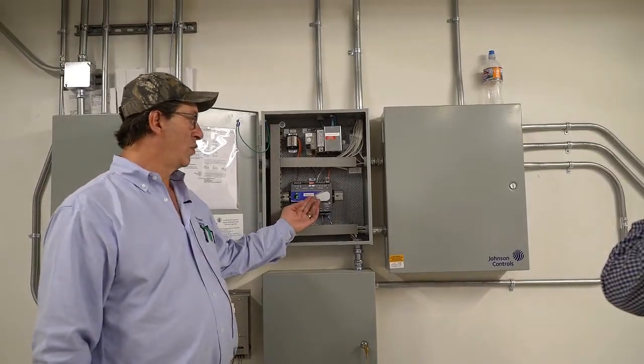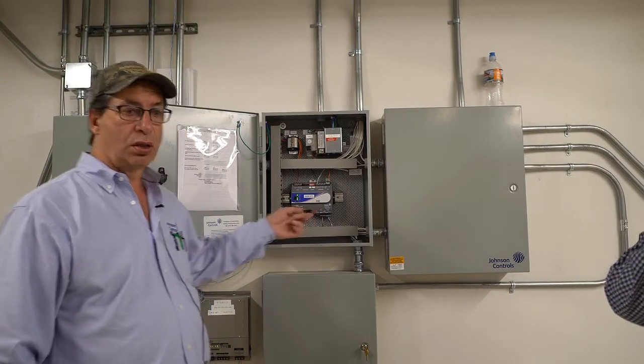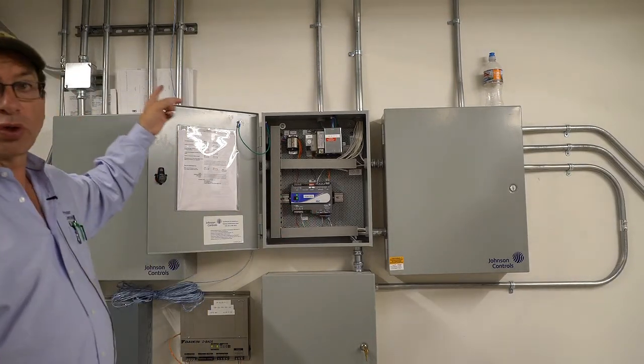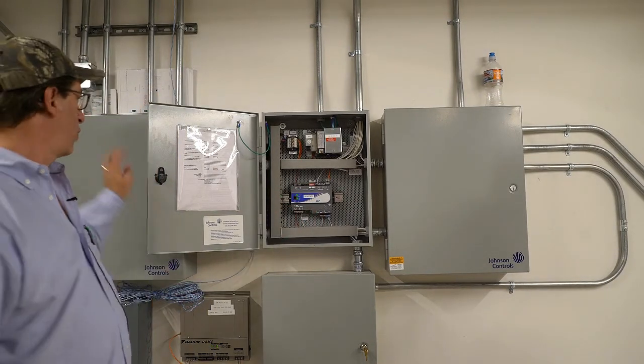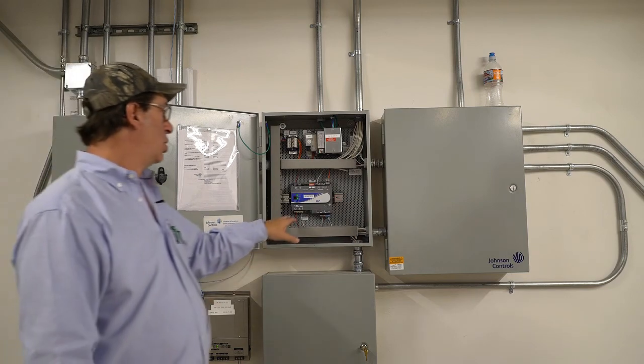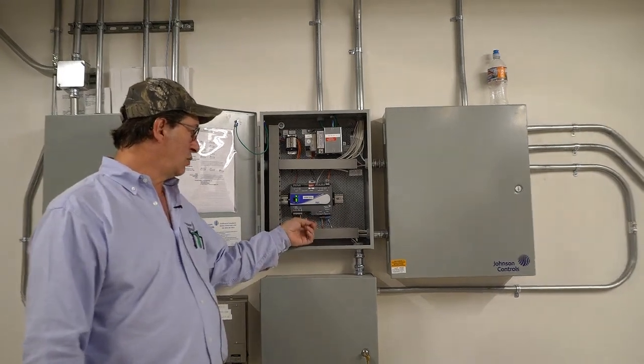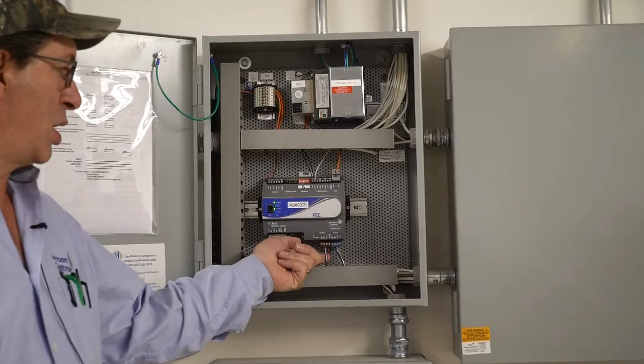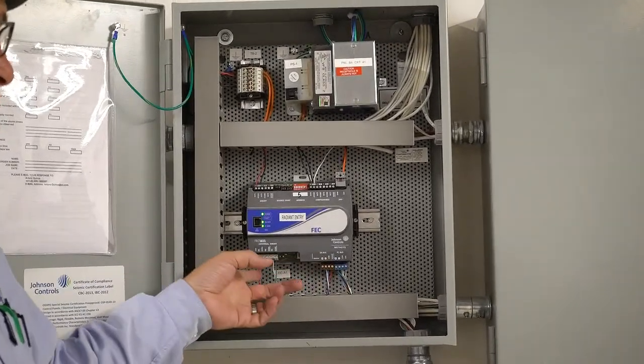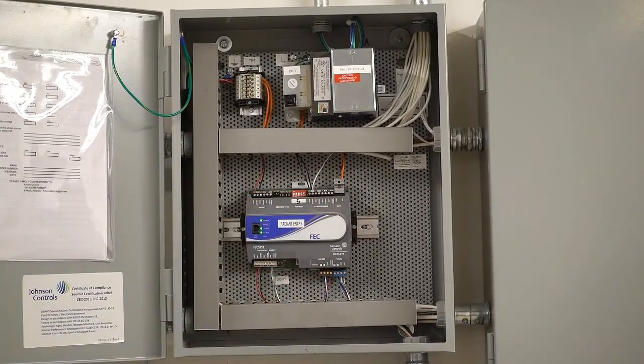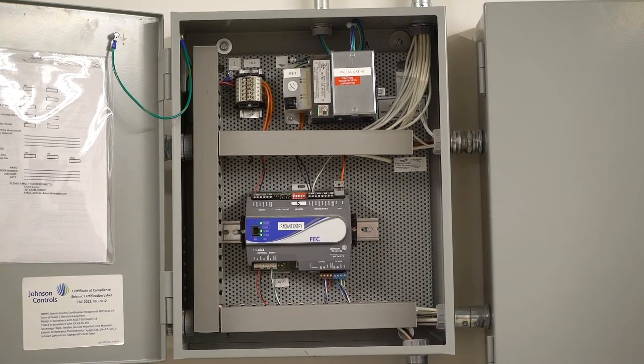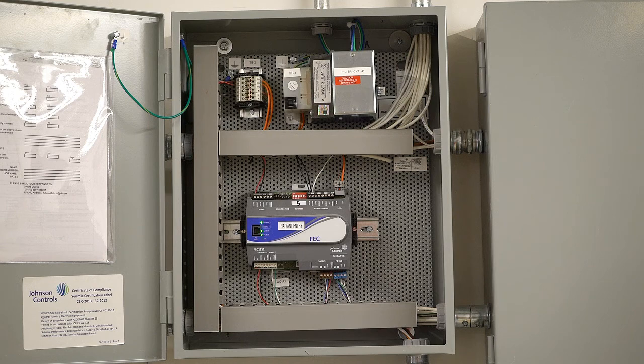So this is the controller for the radiant in the entryway. We'll go down this corridor and we'll show you where the equipment's located too, and the differential pressure sensor off here. So this one has a thermostat coming in here, our trunks daisy chain through here. Then we have our inputs and outputs for a supply fan command, supply fan status, and then we have a temperature sensor, and then we have the output going to the three-way mixing valve.